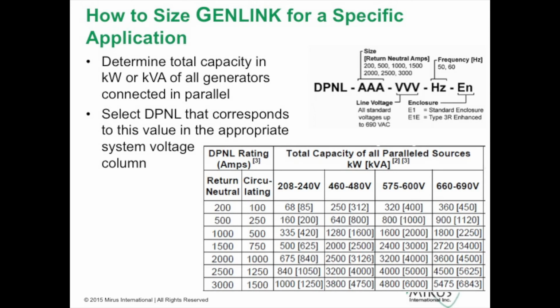You look at your system voltage rating, and then you'll select the size of the DPNL based on the size of the total generating capacity. So if you have 2,000 kilowatts on a 480 volt system, you would use a 1500 amp DPNL. The 1500 amp is the return neutral current rating. It also has a circulating current rating, and that is always going to be half of the return neutral current rating.